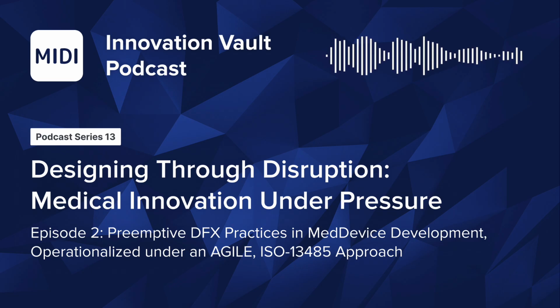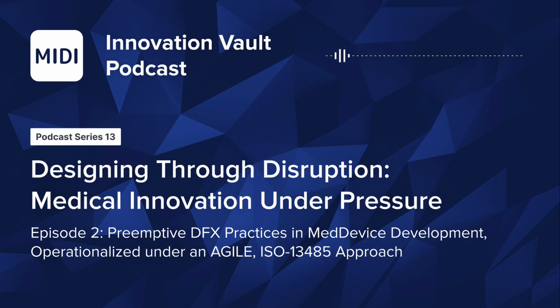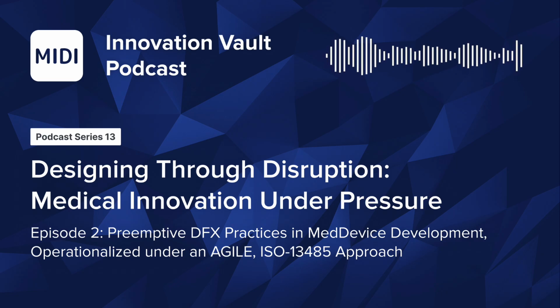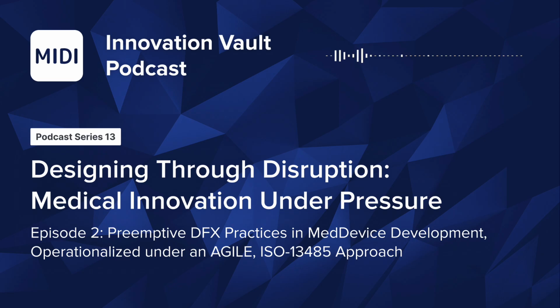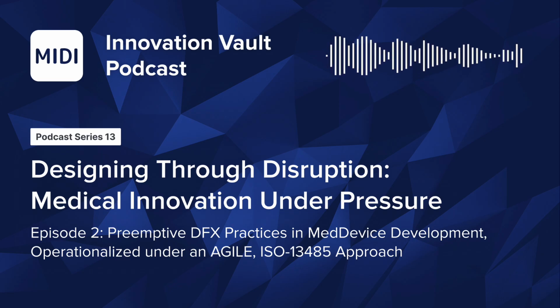It's a step-by-step approach for identifying and tracking in MIDI's cloud-based DHF, meaning design history file. We track all the possible risks, such as the DFMEA, which is design failure mode and effects analysis, where we look at the functional design risks, developing methods of mitigation to reduce risks, thus enhancing the safety of the device. We also look at PFMEA, process failure mode and effect analysis, which scrutinizes a device's design and identifies any potential manufacturing and assembly risks that may occur during the manufacturing process or human error.